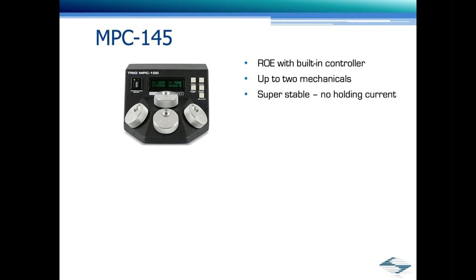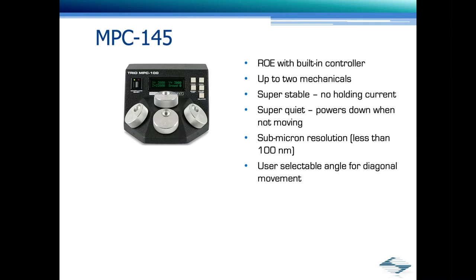Super stable, no holding current. Super quiet, as it powers down when there's no movement. Sub micron resolution movements, less than 100 nanometers. Has a user selectable angle of 0 to 90 degrees for diagonal movement. Has four selectable speeds. If you prefer ROEs in your setup, multiple ROEs in your setup, you can mix and match the controllers to get exactly what you need.